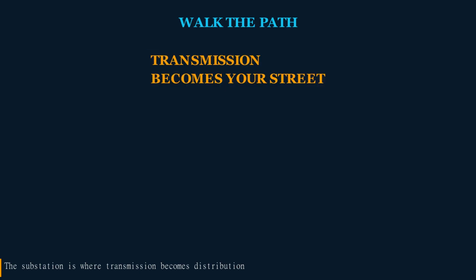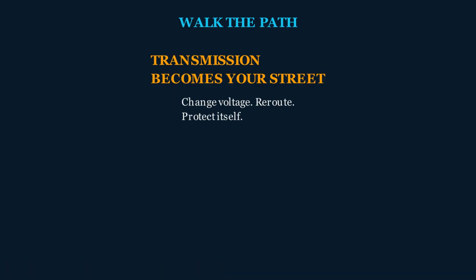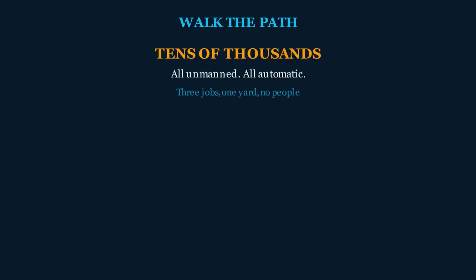That's the substation. It is the single point where the transmission grid becomes the distribution grid, where the highway becomes your street. It's the one place the grid can change its voltage, reroute its power, and protect itself from its own faults, all in the same fenced yard. And there are tens of thousands of them across the country, almost every one of them unmanned, sitting quietly, doing all of this on its own.